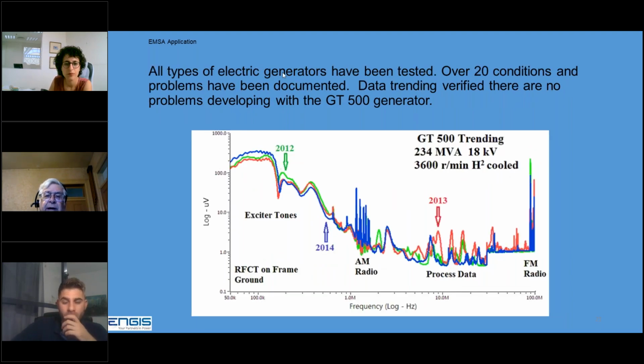Many types of electrical generators have been tested. Hydro generators, internal combustion engine driven generators, steam turbines, combustion turbines, nuclear turbines. A lot of generators have been tested. We'll get into it later, but we found over 20 conditions and problems that have been documented. Most of these can be identified on the first test. Data trending is good. It's particularly good to verify that no problems are developing or that a problem is developing.